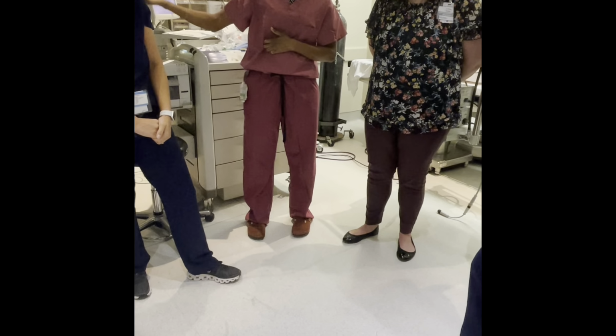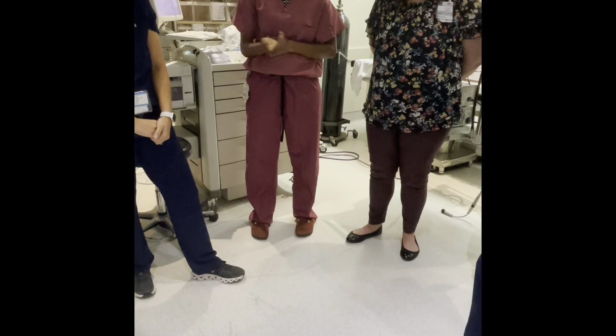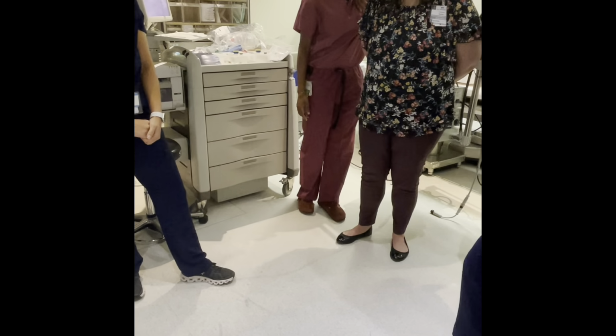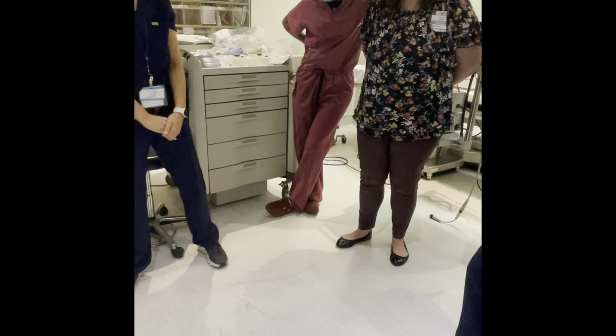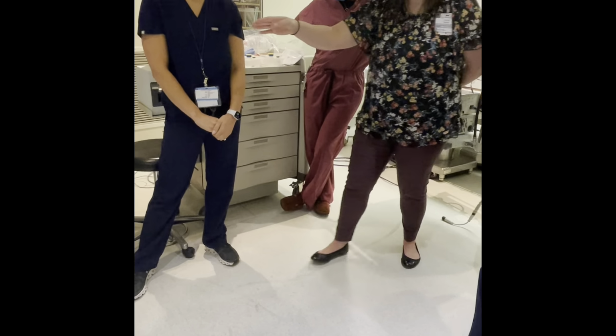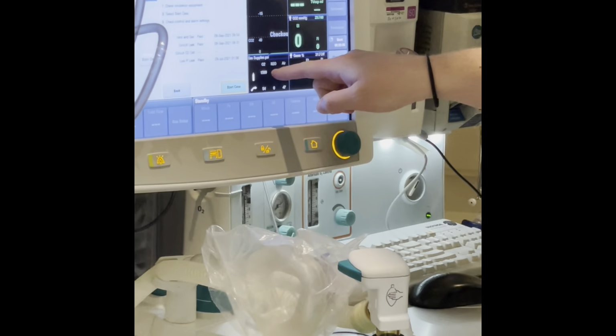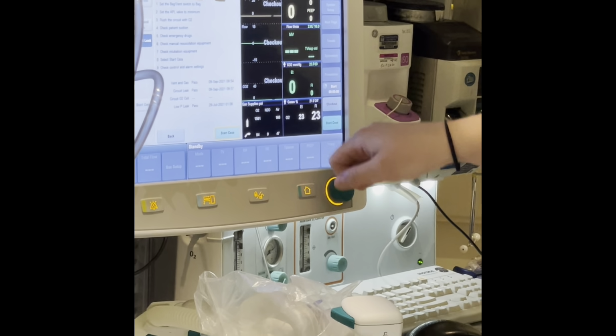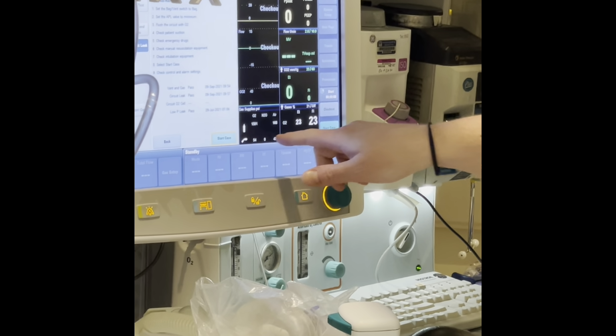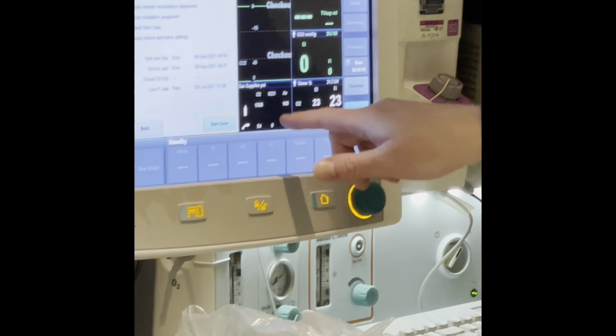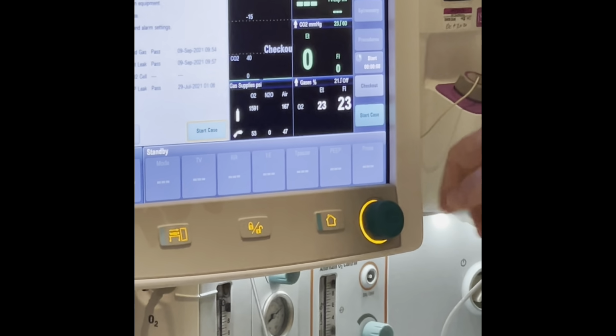So that will be the time when that alarm will come on. Okay? Sorry. No, you're fine. So yeah, part of your check will be opening the cylinders and checking their pressure. And on this machine, you can see the pressure will read next to the cylinder. So the O2, the PSI is 1590, air is 167. And then this is your pipeline pressure. So 5447. So like we said, the pipeline should be around 50.